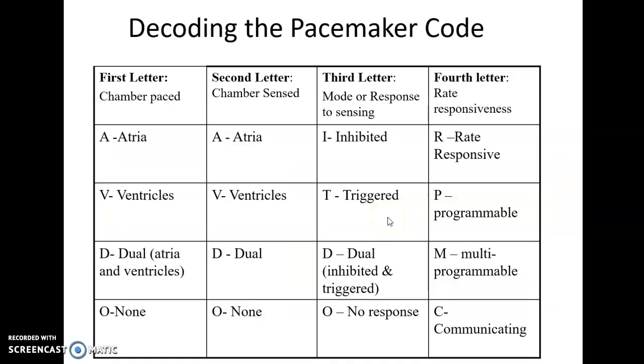Now, it's always a nice thing for patients to know what their pacemaker is supposed to do. And normally when a person has a pacemaker inserted, they're given a card that will tell them what the pacemaker does so they can pass that information on if they ever get admitted to a hospital. But let's face it, in reality, many of our patients come in and we see that they have a pacemaker because we see the hard lump under the skin, or we put them on the monitor and we see they're in a paced rhythm, and we ask them what type of pacemaker they have, and they have no clue. So pacemakers have a code to them, a pacemaker code. And it'll give you an idea of what we should expect that pacemaker to do.